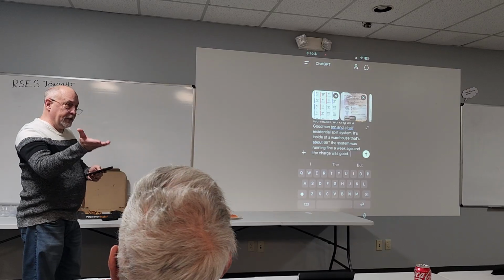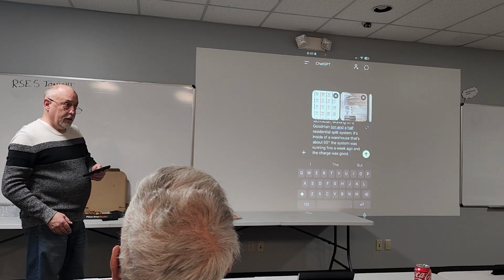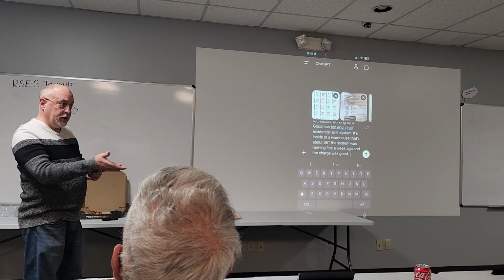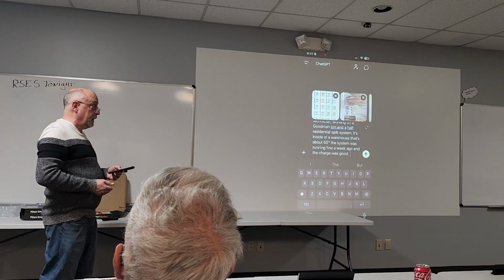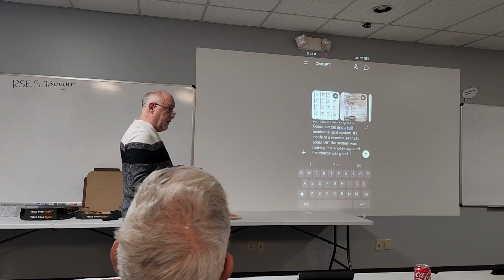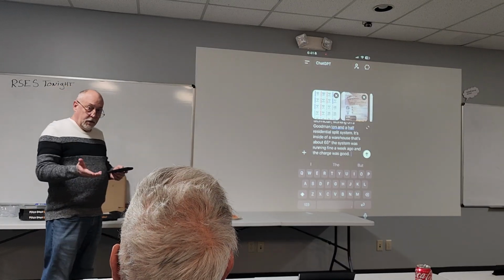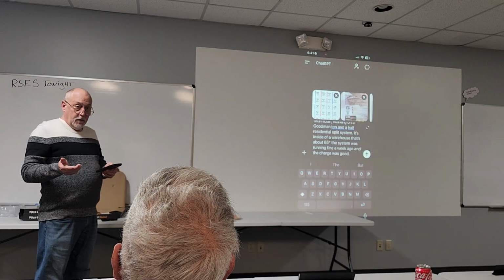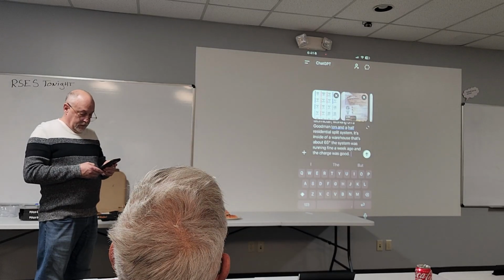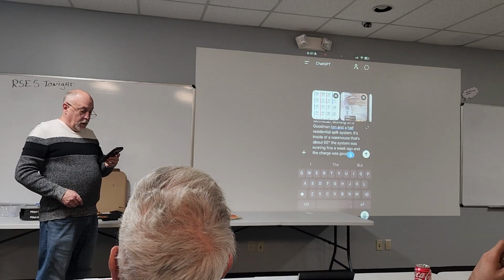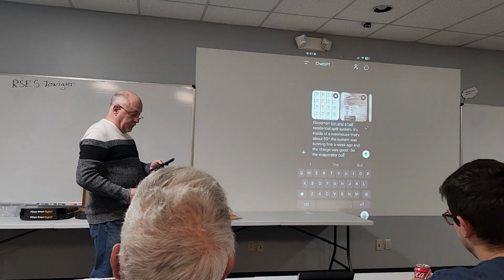What do we check? What things could we tell if we check? The load in the house. Yep, so we know it's low load in the house, but what things could you check? Airflow. So we could say airflow. Coil was clean, filter was good. So the evaporator coil's clean, and the filter's clean.